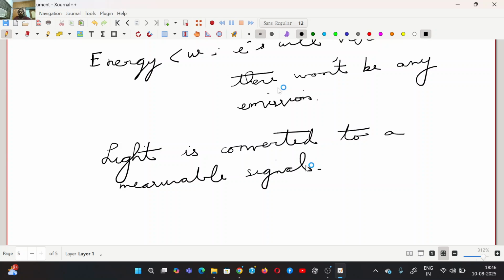And the more the absorption, that means the trace metal that we want to detect is more in amount. So it absorbs most of the light, the light striking the detector will be less, and the signal will also be weak. But if the trace metal is very less, it allows most of the light to pass through, and there will be more current. Like that, they make the calculations in the machine. So that's the journey of the light from the lamp to the detector.